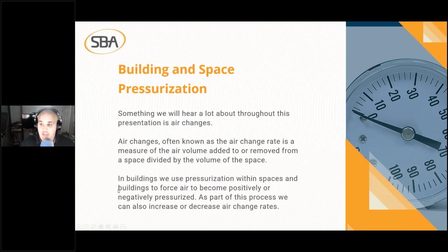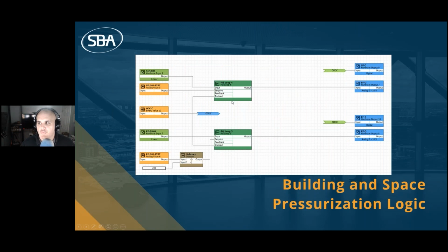You'll see this in isolation rooms where we don't want the air to escape from the isolation room. And usually those rooms will have a dedicated exhaust. Now, as part of this process, we can also increase or decrease air change rates because if we are exhausting more air in a space or we're supplying more air to the space and forcing it through the exhaust, then we're changing the volume of the air. And the faster we change the volume of the air, the faster that we will have air changes. That'll become important when we look at the mitigation strategies around outdoor air and humidity later in this presentation.